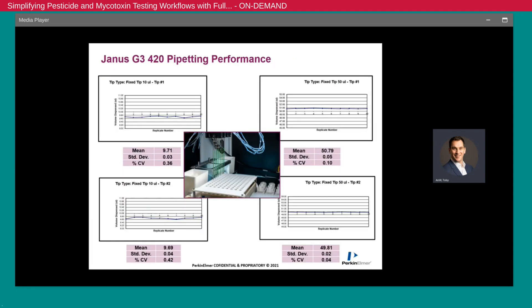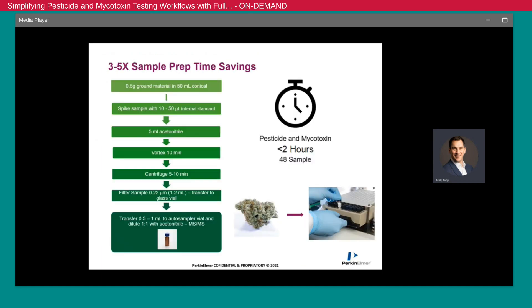We wanted to be very cautious about replacing a manual workflow that has very high performance requirements. What we were able to do is compare and evaluate the manual and the automated workflow, and found the automated workflow to have equivalent or better performance than the manual workflow. This gives us confidence that these automation workflows are viable in the cannabis testing environment. We confirmed that we can prepare 48 cannabis samples in less than two hours — a similar task that takes labs upwards of four to five hours manually — while also allowing the lab to allocate staff to other tasks during sample preparation.